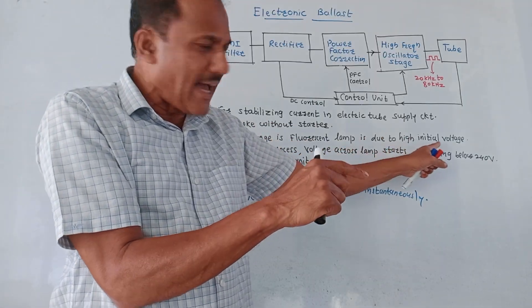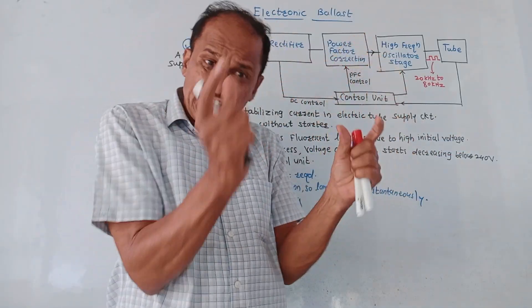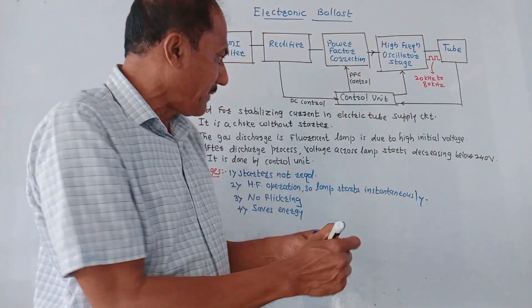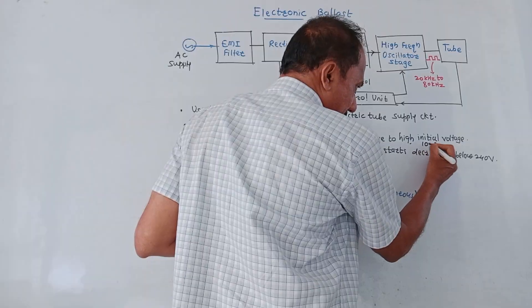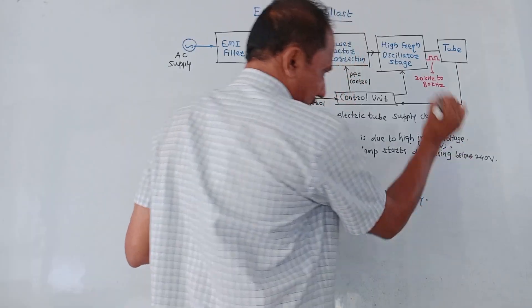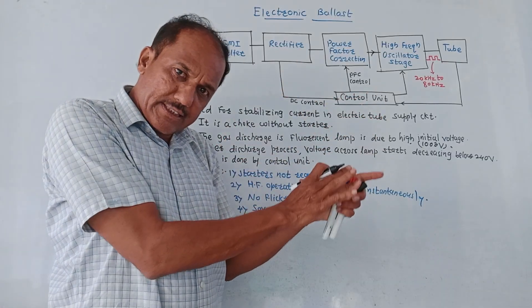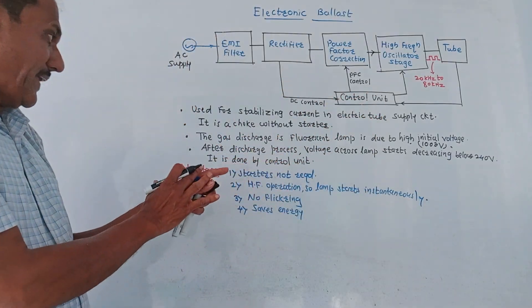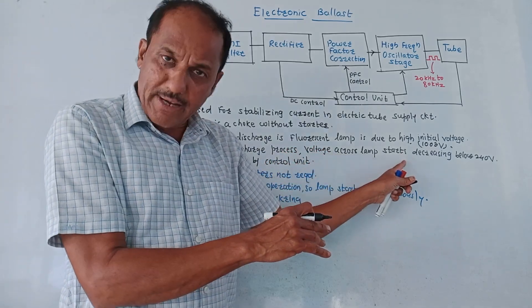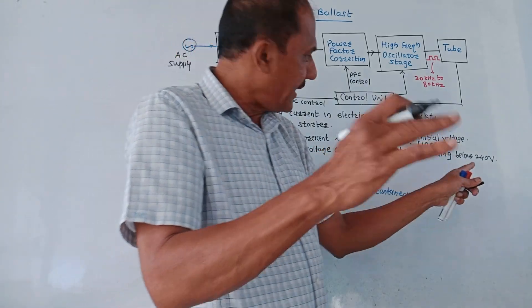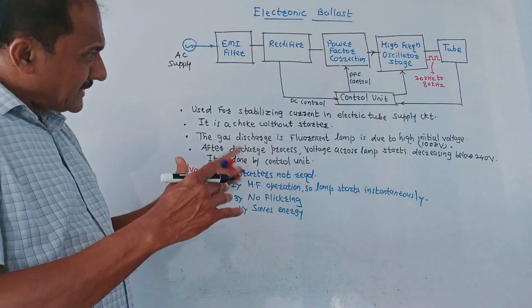...is due to the high initial voltage. That means if you are talking about a fluorescent lamp, then initially the gas discharge inside the fluorescent lamp takes place. This is due to the application of high initial voltage which is around 1000 volt. So due to this higher voltage, the gas discharge inside the fluorescent lamp takes place. After discharge process, the voltage across lamp starts decreasing and it will be around 240 volts.